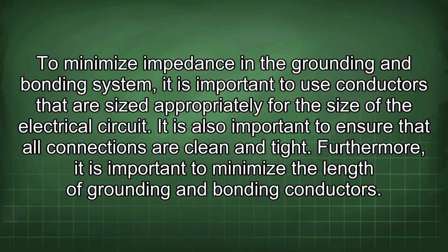To minimize impedance in the grounding and bonding system, it is important to use conductors that are sized appropriately for the size of the electrical circuit. It is also important to ensure that all connections are clean and tight. Furthermore, it is important to minimize the length of grounding and bonding conductors.